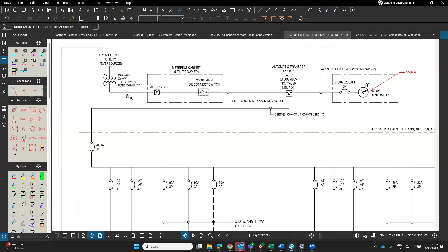Okay, so we're getting service from Eversource. We're requesting a new 2000 amp service, so they'll bring in a new transformer, 480 volt, 2000 kVA. I've been coordinating with the representative from there to make sure we're on the same page with where the transformer is going to be located, and all the conduit and wire going to the transformer from the poles. That's all going to be Eversource's design, and they're going to put together a work order and figure out how they want to put that transformer in.